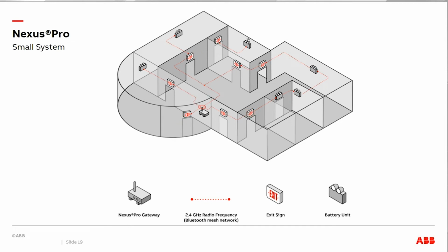As a note, Nexus Pro is a system that can only work with battery backup or single point fixtures. We are not able to run these off dedicated AC-only fixtures, meaning fixtures running off a 120 or 277 volt entrance. These can only run off battery backup units—the Nexus Pro is only able to monitor battery backup units.